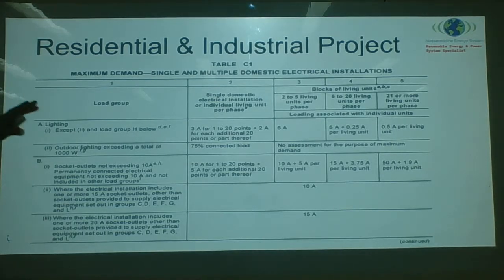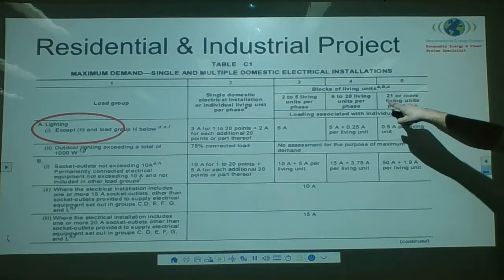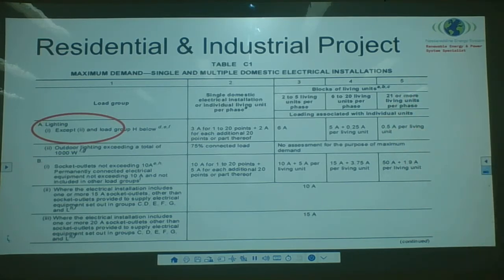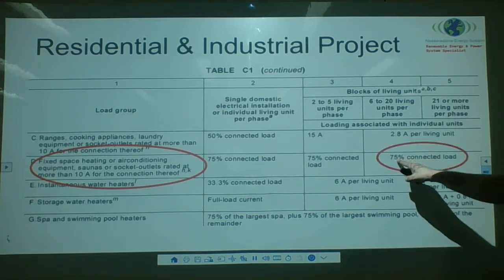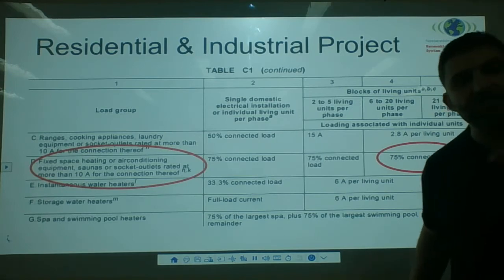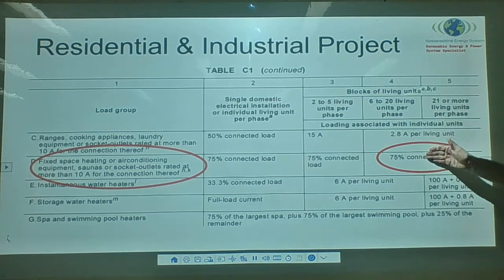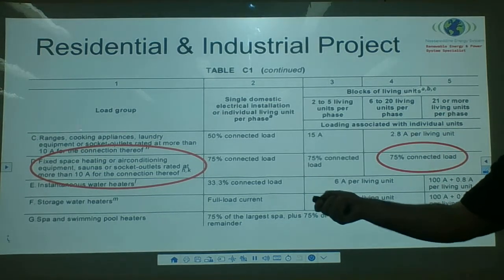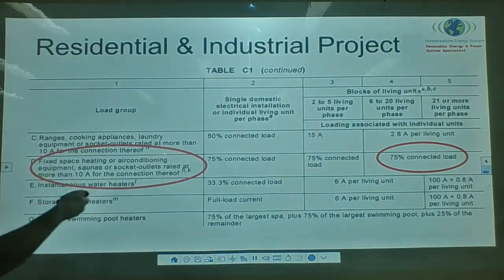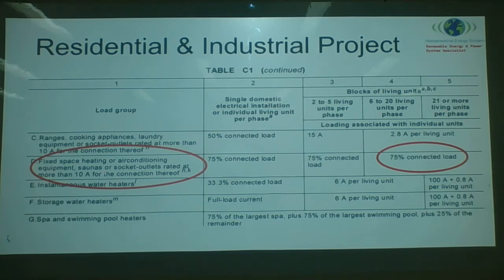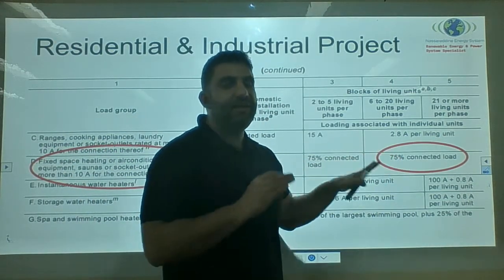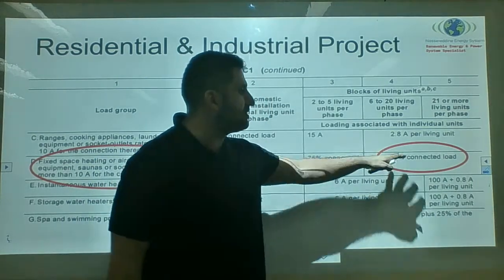From the Australian standard: if you have 21 or more living units per phase, lighting is allowed at 0.5 per unit. For heating and air conditioning the diversity factor is 75% of connected fixed space heating or air conditioning load. Socket outlets rated more than 10 amps follow other connection rules as explained in the standard. It's very important to follow this — I have never seen a standard that recommends using 100% of the connected power.